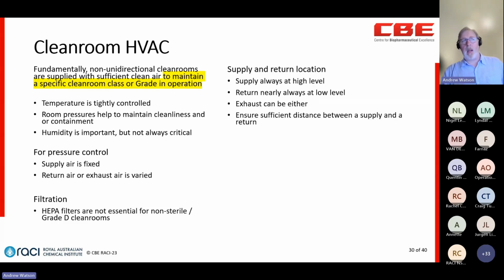You always have your supply at high level, and you should always try to have your return at low level — that gives you a much better clean room. You can have an exhaust either up or low, depending on what you're trying to do with it. You need to make sure you've got sufficient distance between supply and return, because you're providing this clean air into your clean room to dilute your contamination, and you need to make sure it's well distributed.